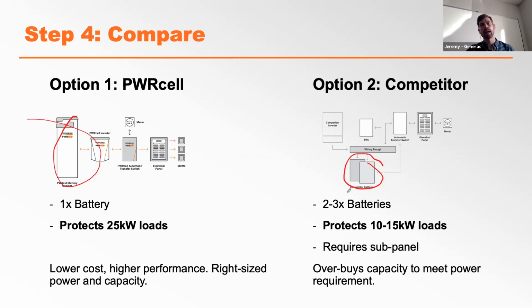More commonly, you're not going to see that kind of apples to apples comparison. You'll see 1 or 2 batteries with a sub panel. In this case, you're still typically quoting and selling multiple batteries, which is too much capacity, and you're still covering just part of the loads in the home, in that sub panel. Even with all those batteries, some unfortunate coincidence could black out that system. If some combination of loads turned on, depending on the battery manufacturer, that may or may not be recoverable over the course of that grid excursion. You might be stuck without power when the grid's down if you don't have load management.